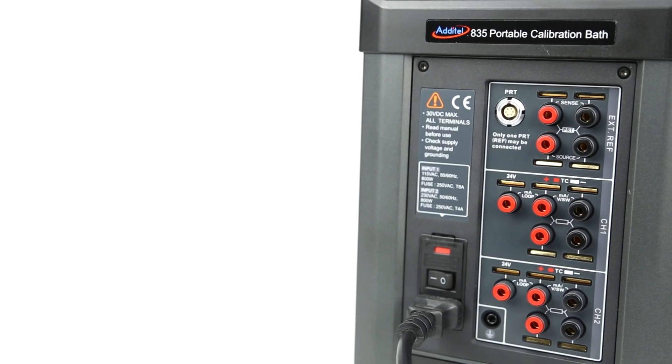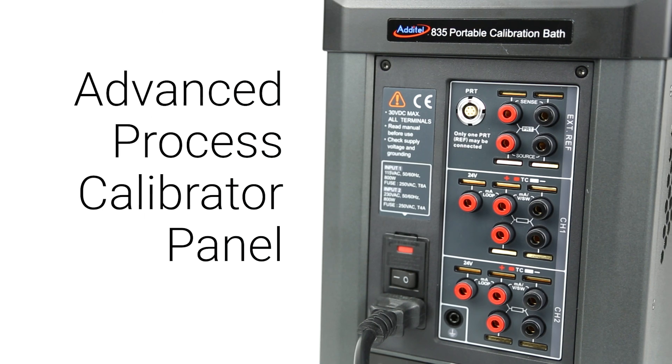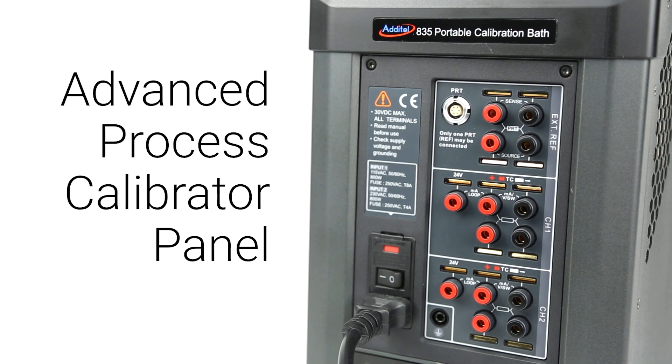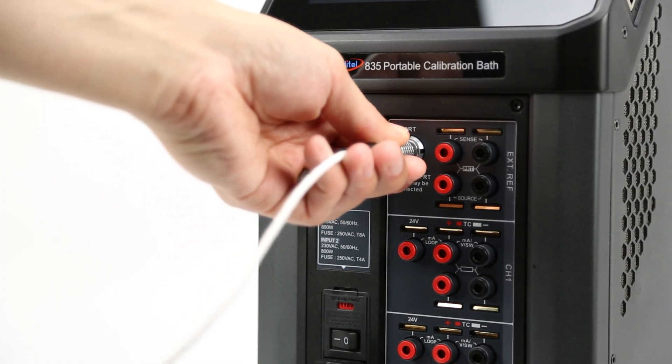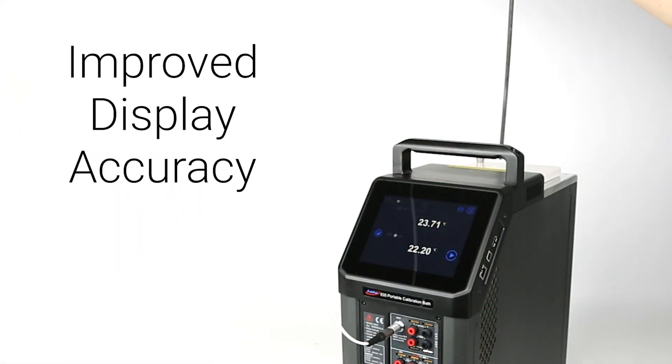Sensors can be attached to the device through any of the inputs available on the 3-channel process calibrator panel, which includes quick push, 4-wire, and thermocouple connections. Also included on the panel is a LEMO port, allowing users to further improve display accuracy with a reference probe of their choosing.